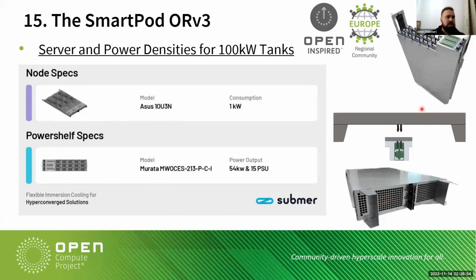This is the Murata power shelf we also tested and validated this year, providing 54 kilowatts. Each PSU provides 3.6 kilowatts and has no fans, since it's made for immersion. Murata also shared that next year they expect to reach 5 kilowatts per PSU, because the immersion environment is very good for this, without the limitations of air cooling. So we'll have more density in less space, and be able to provide more power in less space. This is a 3 OU power shelf, so with 6 OUs we can power 100 kilowatts in our tank.